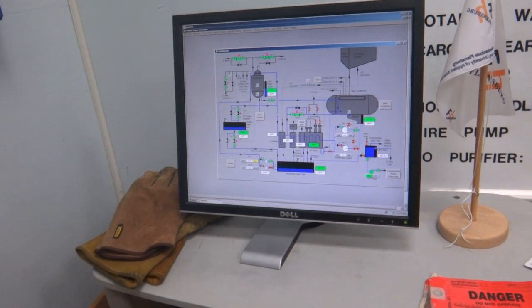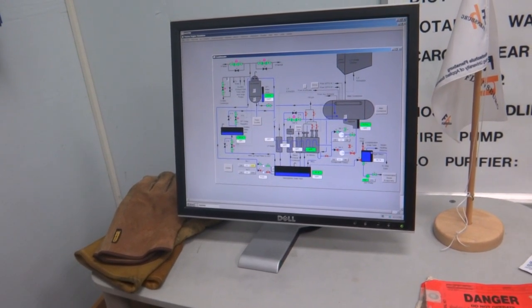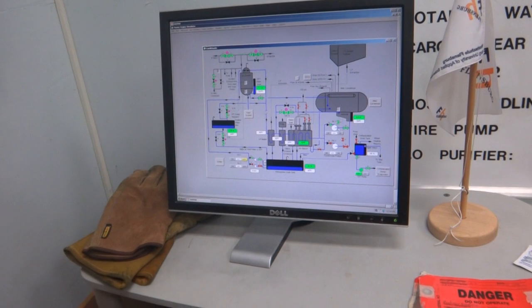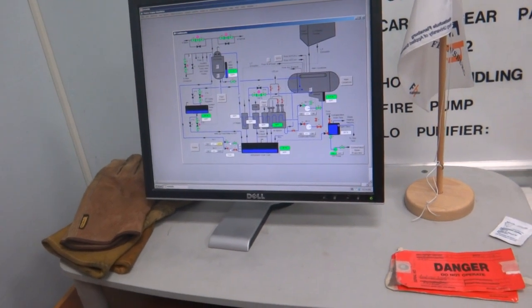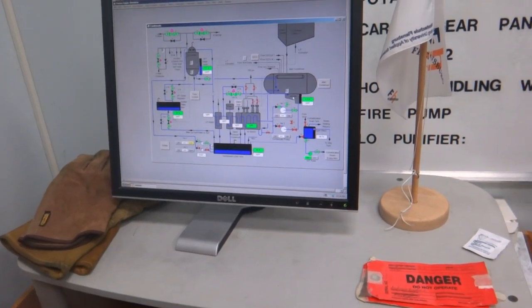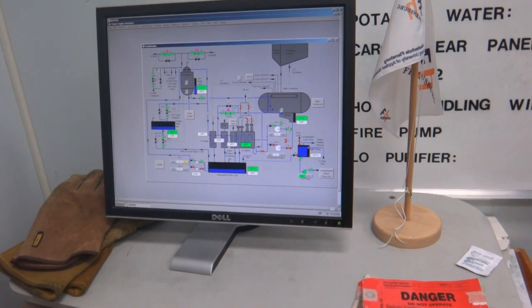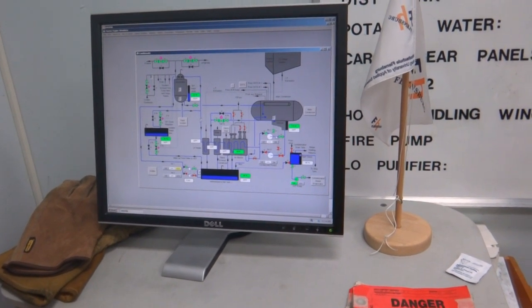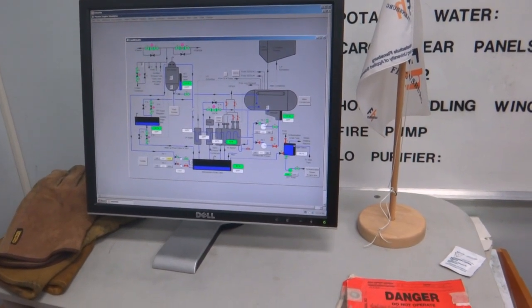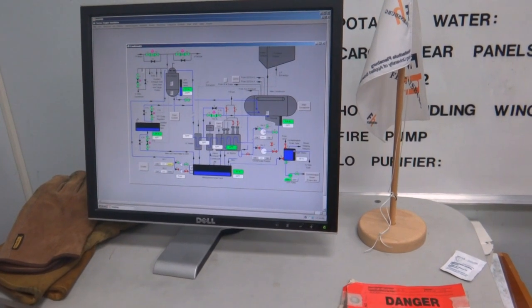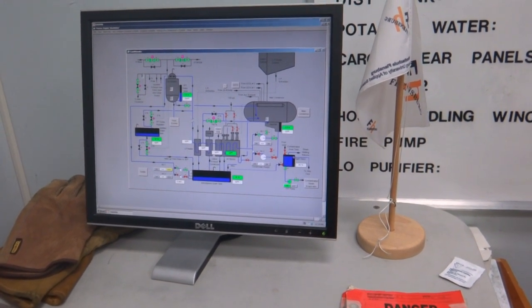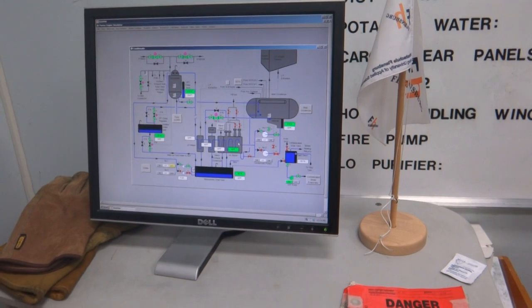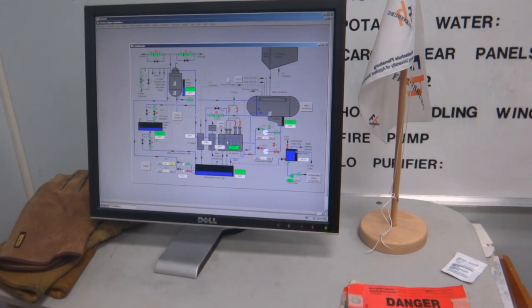Open up the vent line because the lowest pressure is actually the eye of the impeller at the condensate pump. And if you have water coming out of the hot well that's at saturation and hits a lower pressure, what can it do? Some of it will, yeah, flash. So the vent line is very important on a condensate pump because it's running in a vacuum. And then it goes into the inter condenser, then the after condenser.